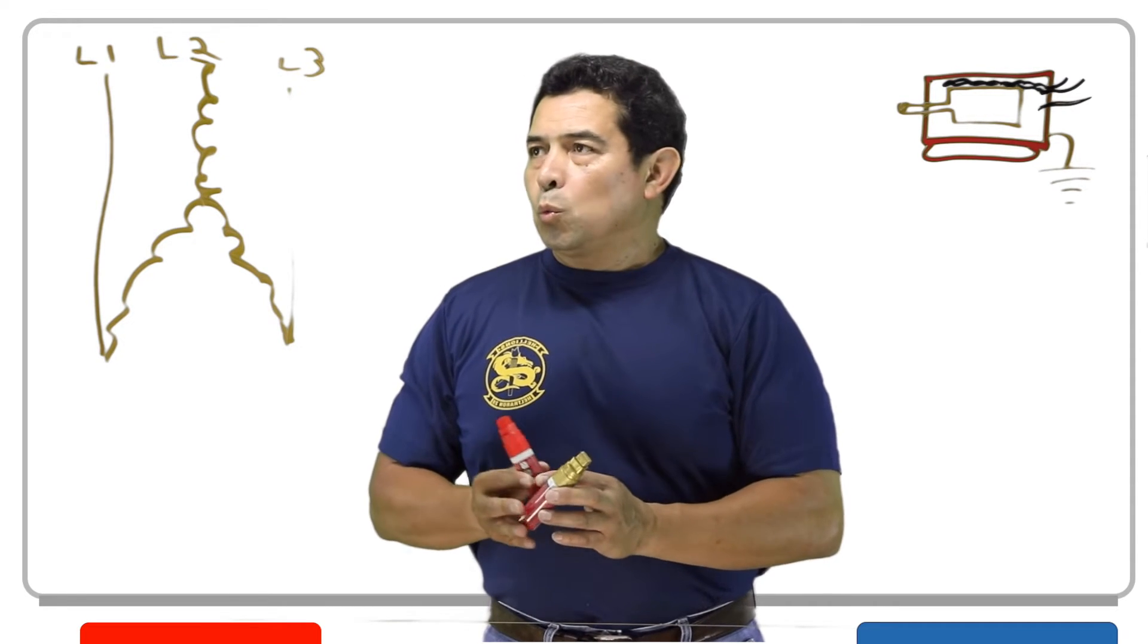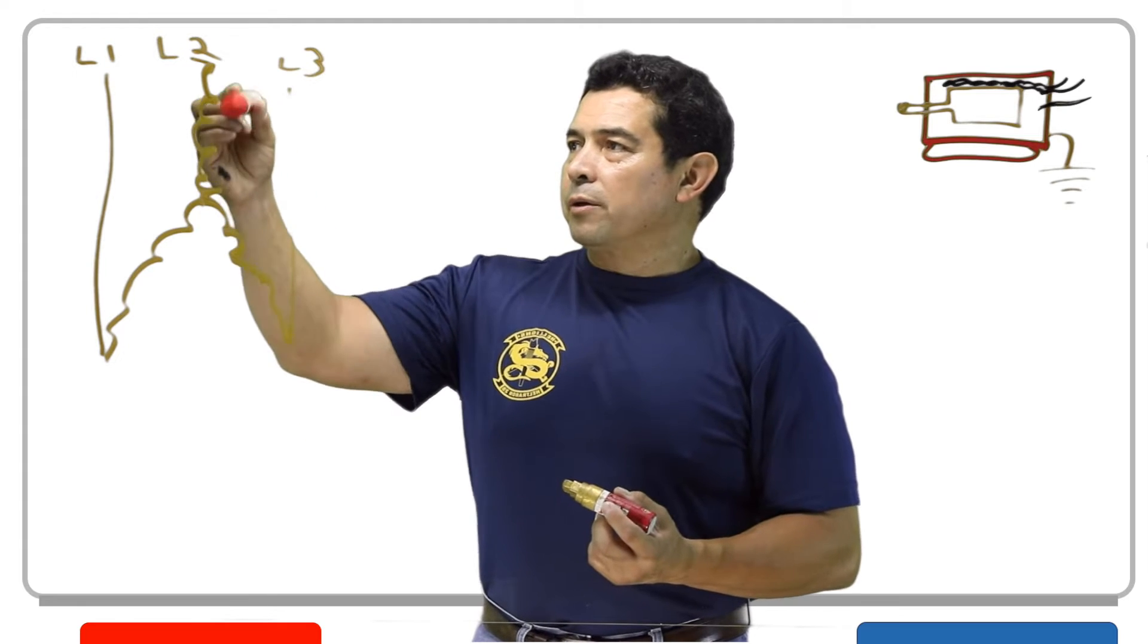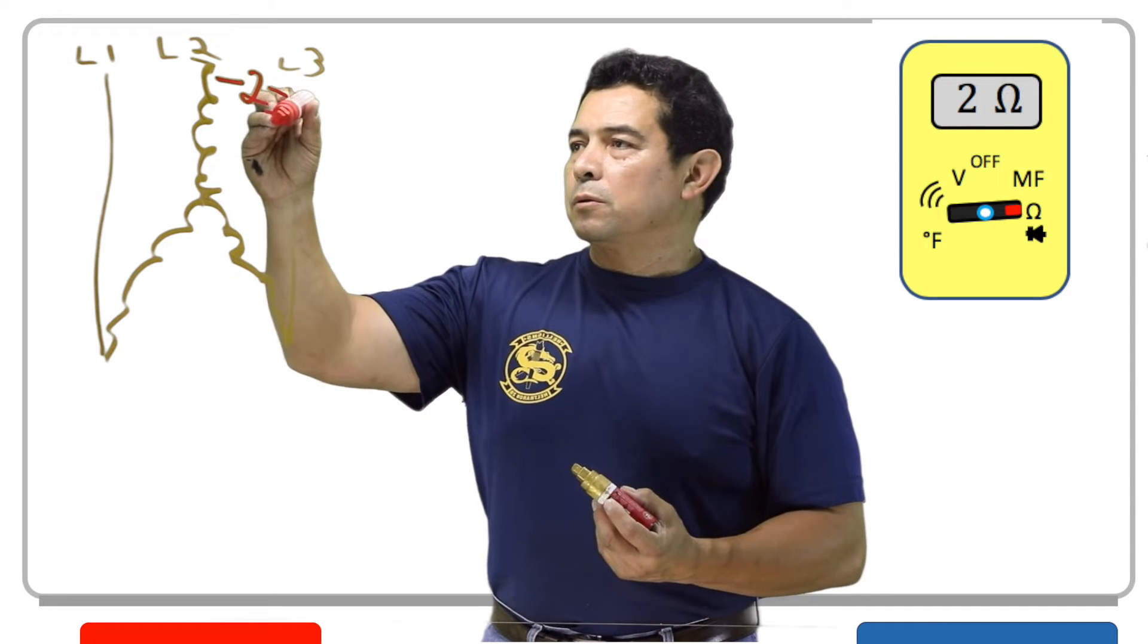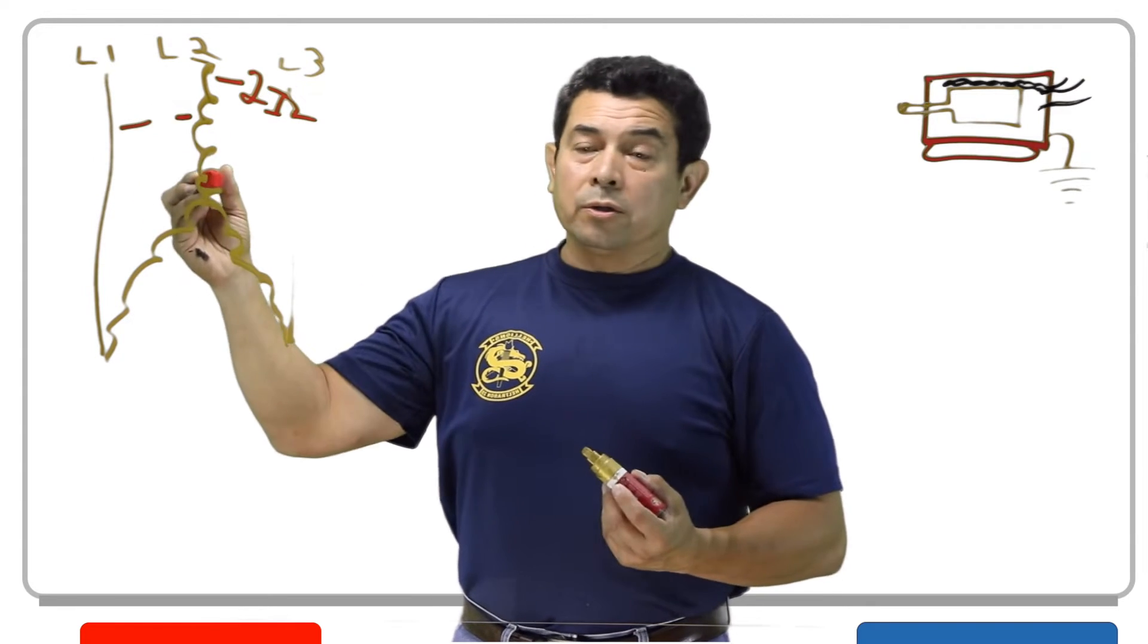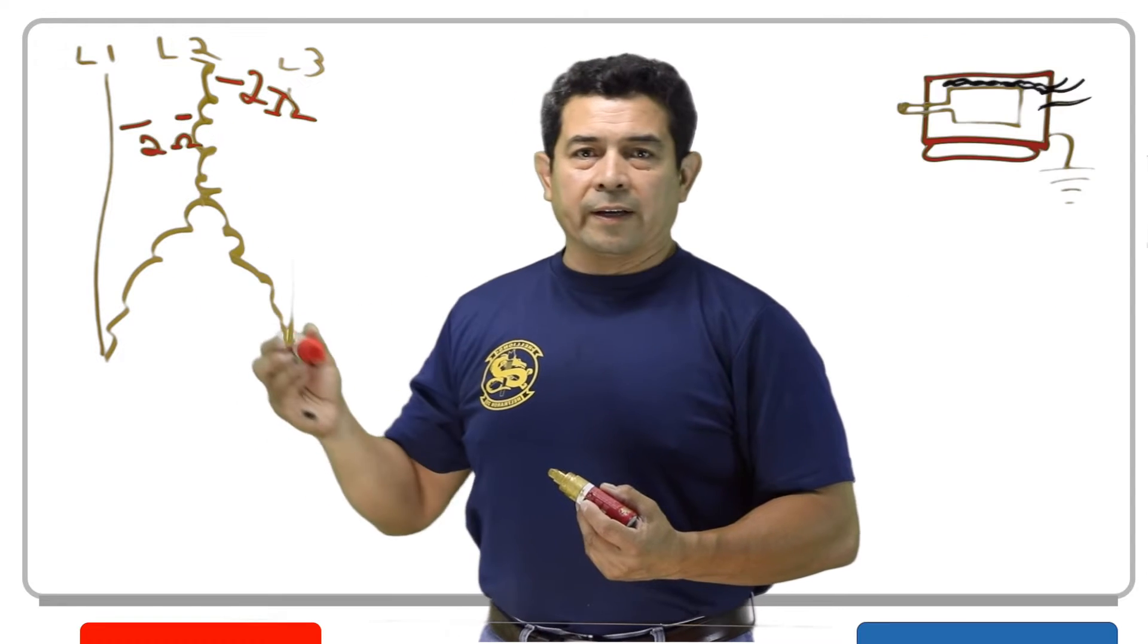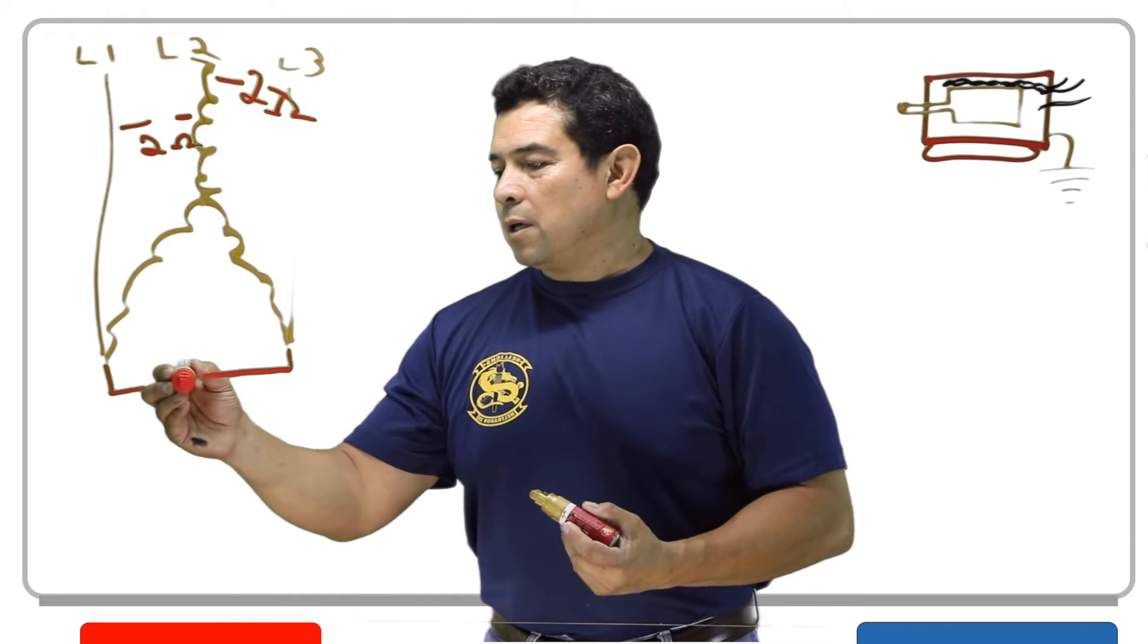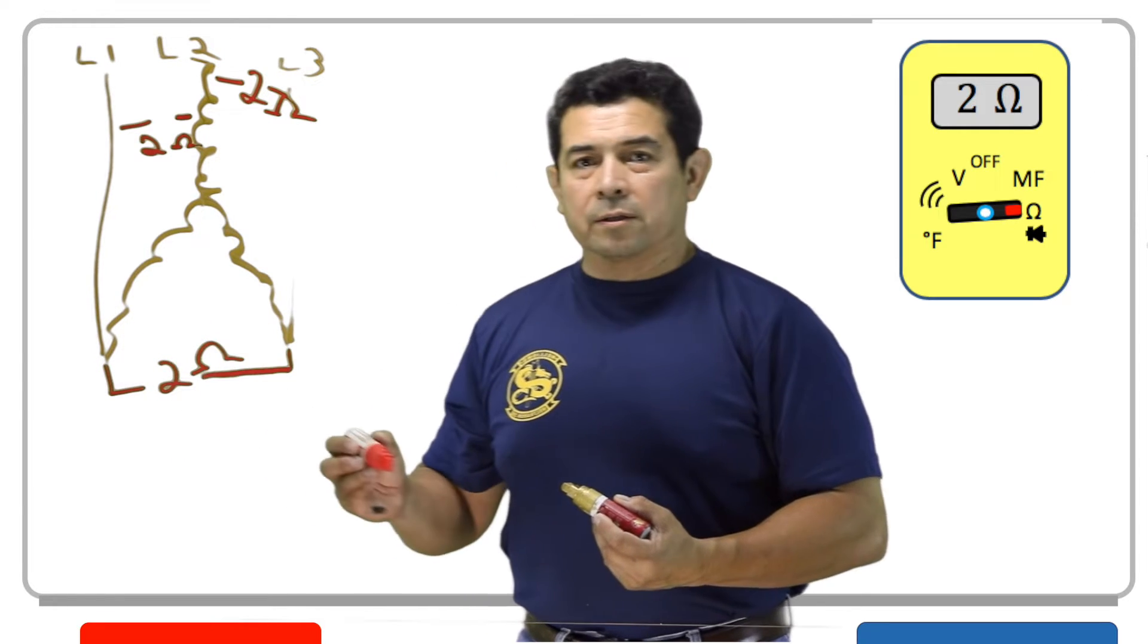So let's say that if we were to troubleshoot this motor, we're going to check from here to here to here, and let's say that we get two ohms, two ohms there. So that means that from here to here, we should also get the same two ohms like that. That also tells me that between this one here and this one here, I should get the same two ohms like this.